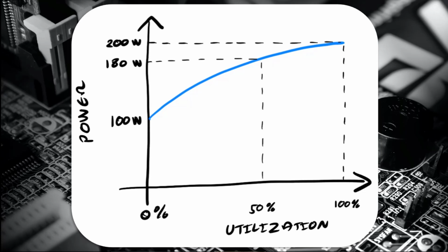And there's this 0% utilization, with a consumption of static energy, which is 100 watts. And if we move to its maximum utilization, using CPU and all the resources to 100%, there's only 100 watts of difference. So it's kind of amazing to think that if you have all the servers idle, they will still be consuming half of the energy of the same scenario as having them running at 100% utilization.